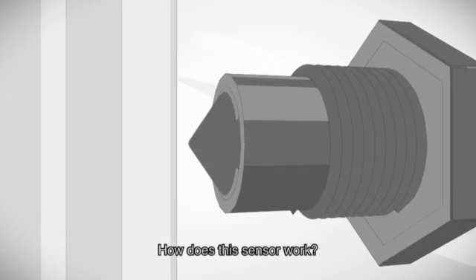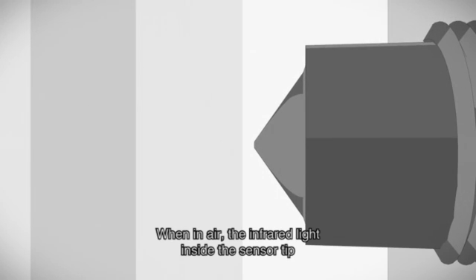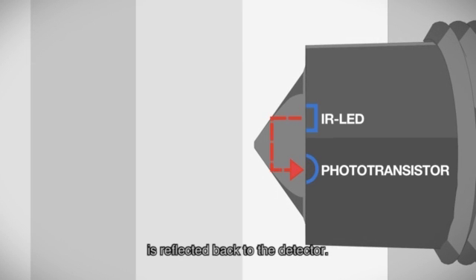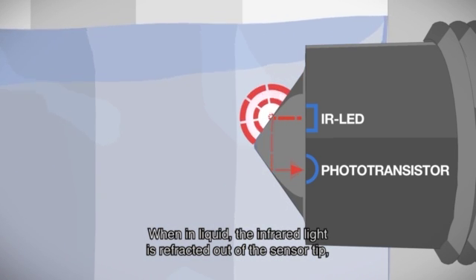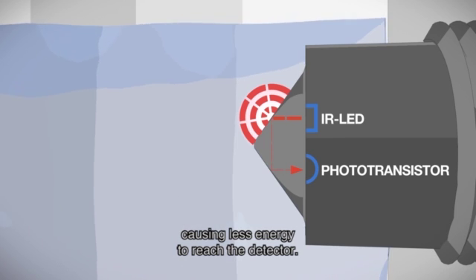How does this sensor work? When in air, the infrared light inside the sensor tip is reflected back to the detector. When in liquid, the infrared light is refracted out of the sensor tip, causing less energy to reach the detector.